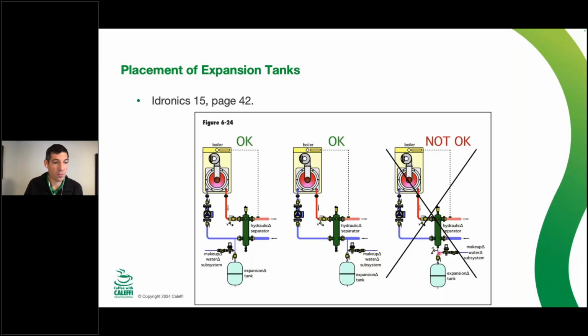One place we don't want the expansion tank is right below it, because all this dirt is going to collect here and then it's going to fall down onto the diaphragm or the bladder of the expansion tank. We don't want a bunch of dirt sitting there. Also, as the temperature of the system changes and the expansion tank works as it should and it expands and contracts, it could just inject all that dirt right back into the boiler, which we don't want. So we don't want the expansion tank right there, having flow up and down through this vessel from the bottom isn't good. That's where our dirt collects. We want to do it to the left or the right in this scenario, but either would be acceptable.